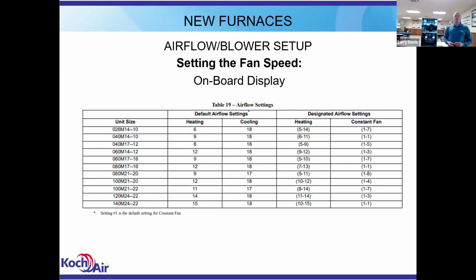Default settings. I mentioned before, they're going to come out of the box with the default setting. Based on what furnace it is, this is an example of the base tier furnaces, the Comfort Series furnaces. Depending on the size, it's going to come at a default heat setting, which should be about the mid-range. Your constant fan is always going to be 1. Your cooling is going to be at the highest level.